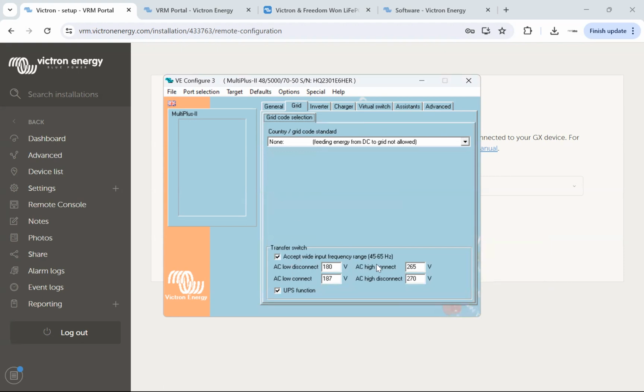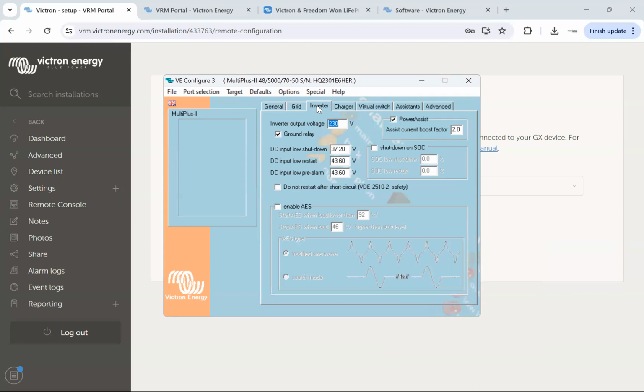We want to accept a wide range of voltages from the generator because generators are typically horrendous compared to the grid. And UPS function basically means as soon as the AC current or voltage or frequency input fluctuates a little bit, it's going to kick it off and start inverting, and it's going to do it as fast as possible like a UPS. Now, if you've got a generator that's even slightly dodgy, it will just kick it off for any random reason, a load change, or the generator just surges for some reason. So I normally disable the UPS function. That will make it hold on to the generator for a bit longer.